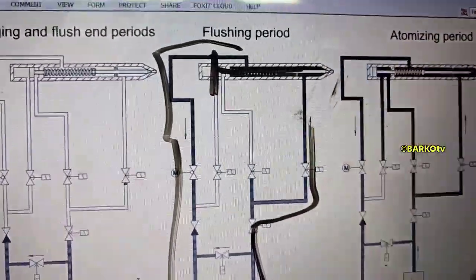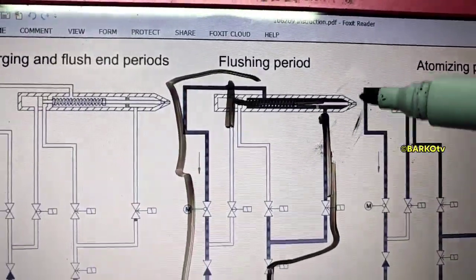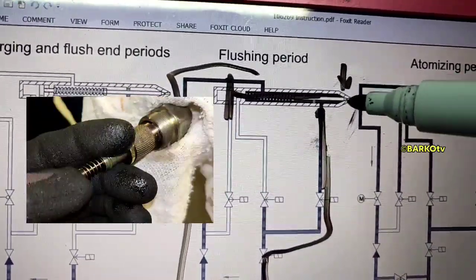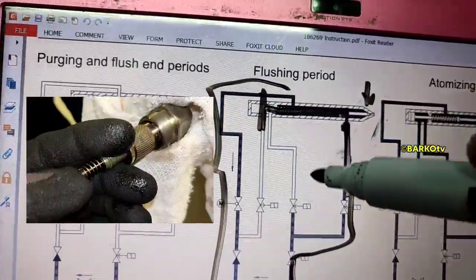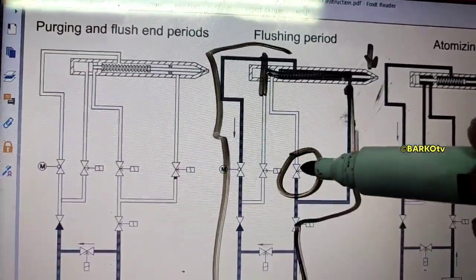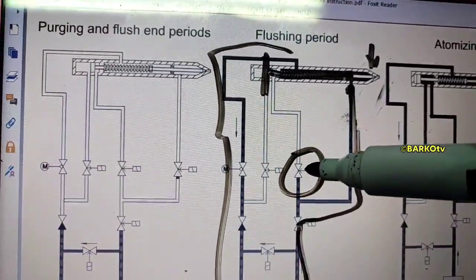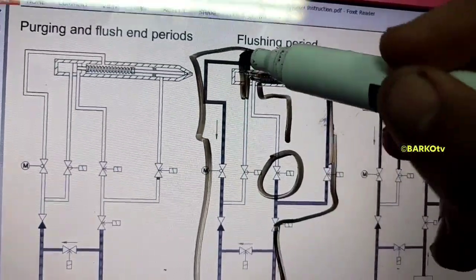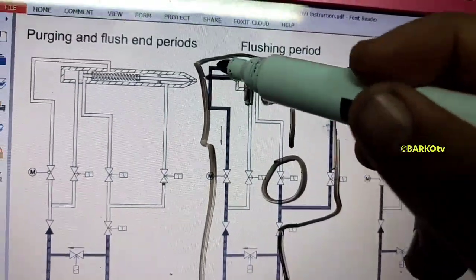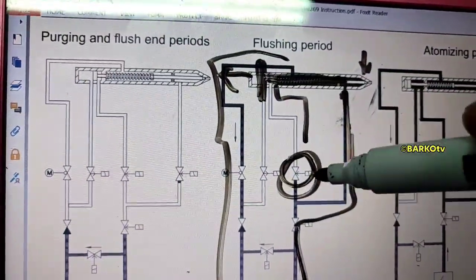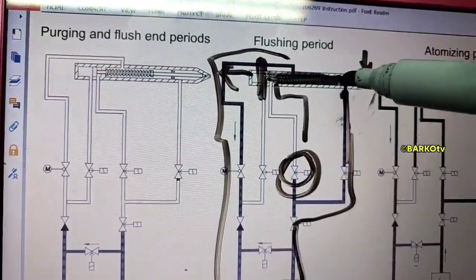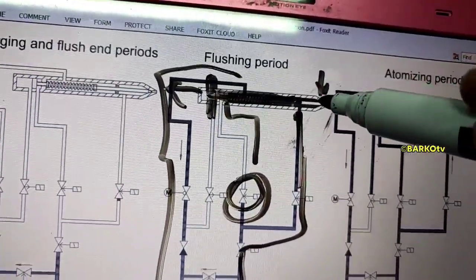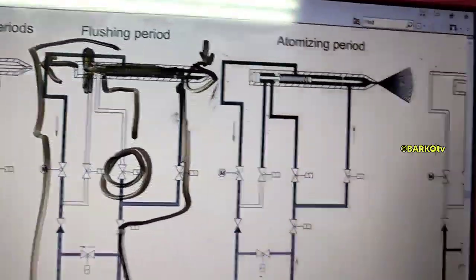As you can see, in the flushing period, there is fuel but the nozzle is closed because there is a shutoff needle installed. Then, after opening this solenoid valve, it asks the pilot to open this piston — the piston goes backward. When this solenoid opens, this piston moves backward, also the actuator rod, and it will release the shutoff needle.